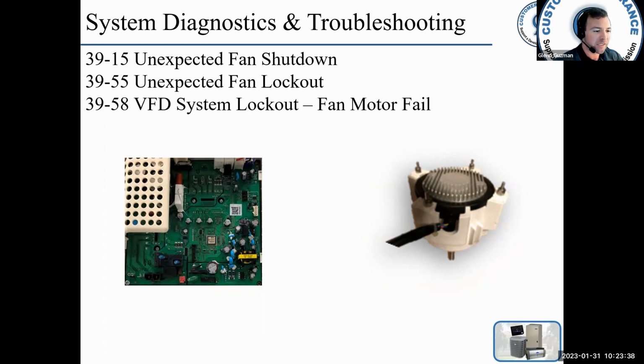The fault can also be set when the speed error between feedback and command is greater than 100 RPM. This fault should never occur because 3915 will be declared after 10 seconds. When this fault is active, the compressor and fan are shut down and the lockout time is 30 minutes.